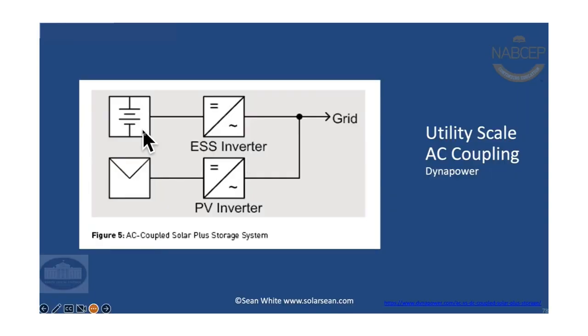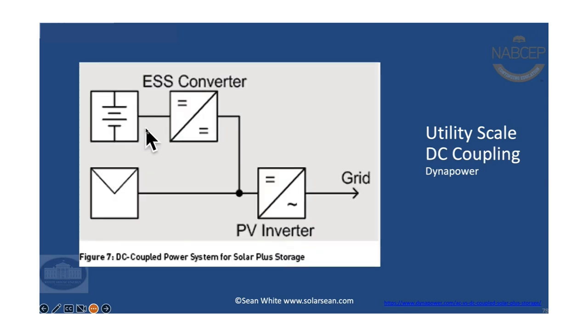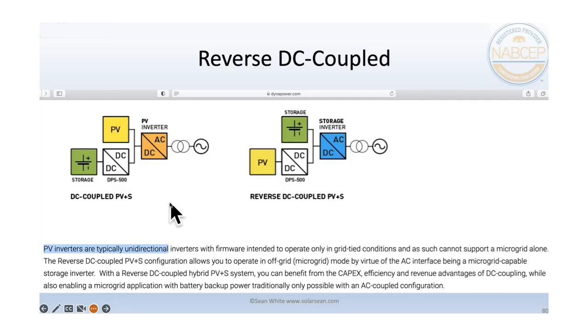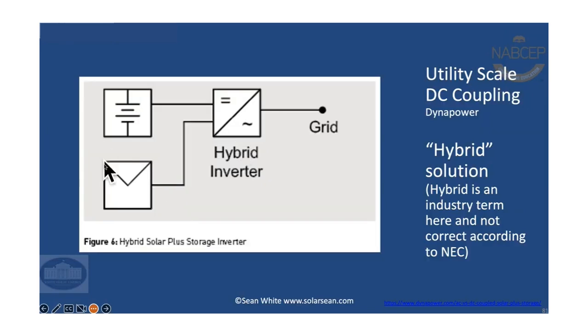So here's AC coupling. The way that I look at AC coupling is that to charge the battery, you have to convert to AC first, and that's called AC coupling. And of course, you only have AC coupling when you are coupling things together, like coupling PV and energy storage together. And then you can have AC coupling, and you can have DC coupling. So this way you could charge the battery without converting to alternating current. A hybrid is a type of DC coupling. It's sort of like you have a charge controller and an inverter in the same box.